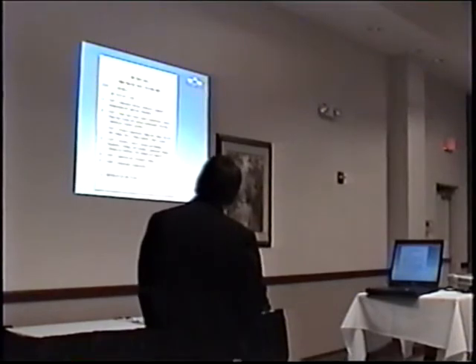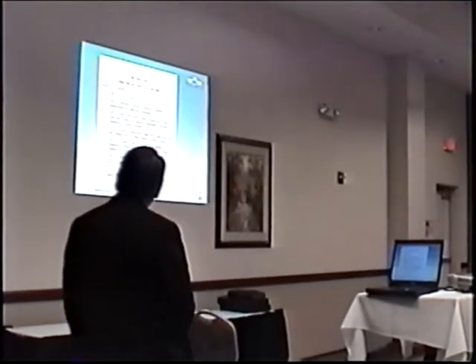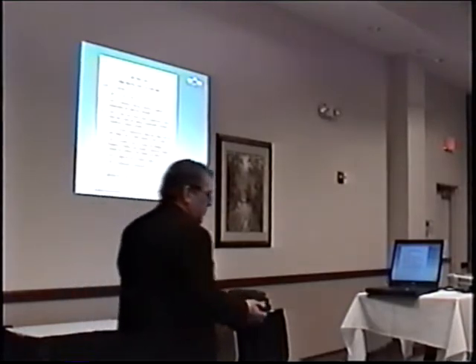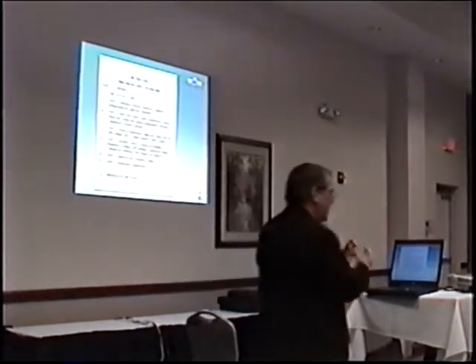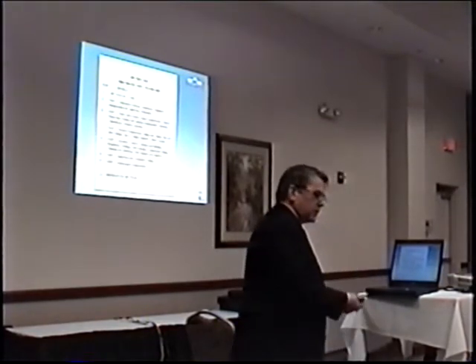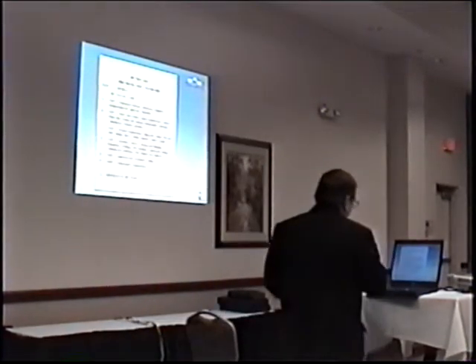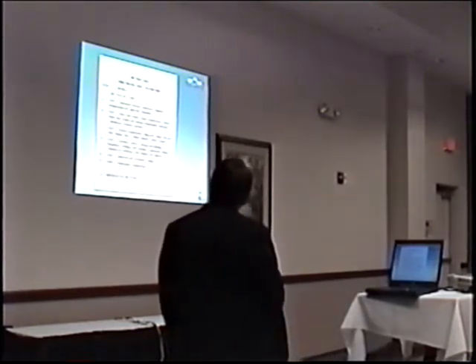I put in the details on the hydraulic calculations, how they should approach that. I even developed tables of equivalent lengths for the different types of fittings. The fittings for high pressure, I didn't bring one because it weighs too much, are not at all like standard sprinkler fittings. So you can't just go to NFPA 13 and say, oh, 1.25 inch tee, I'm going to add 5 feet. So I've developed tables for that. Put it all in there so that they can do their calcs.